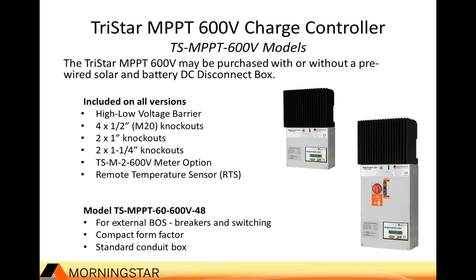On the sides, you'll see a lot of additional knockouts as well that allow pass-through on the bottom to be run, so you can actually string 4 of these together and share a common ductwork through the controllers. And also the remote temperature sensor is included by default with this product because it is a battery charger, so we give you the RTS in the box. Now specifically, the MPPT 600 volt 48 is just the standard controller, and that's the one you see there at the top. That version is just the controller itself, so it has no BOS included. It's just a conduit box. So that would be if you have external disconnects and breakers.